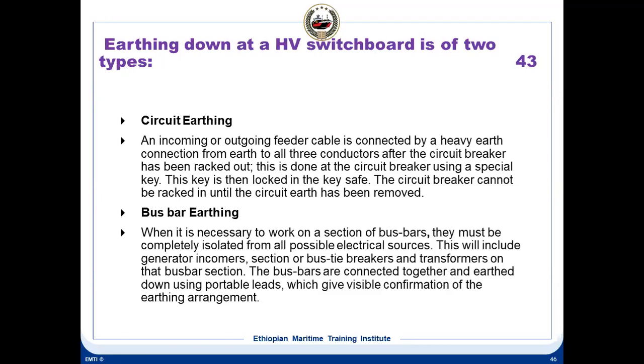And busbar earthing: when it is necessary to work on a section of a busbar, suppose you want to work on the busbar itself, then it must be completely isolated from all possible electrical sources. So if you want to work on, say, number 1 switchboard, you have to isolate, open the tie breaker, and make 1 and 2 switchboards separate. Then this will include generator, incoming, section, bus tie breakers, transformers, etc. And busbars are connected together and earthed using portable leads.